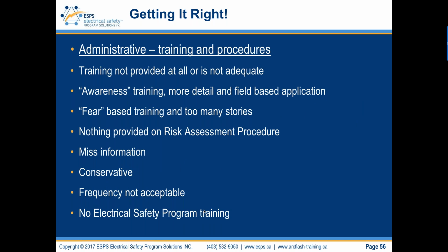You can't just take 8 hours and tell the workers, here's some videos on arc flash and shock, you may be exposed. Here's how to read a label and use the tables, and some brief information on the PPE. It needs to be detailed arc flash and shock training, low and high voltage. Detailed, very comprehensive. And then you're going to get that effective knowledge transfer to the workers, at least in the training. The key after the training is the electrical safety program so the worker can apply it.